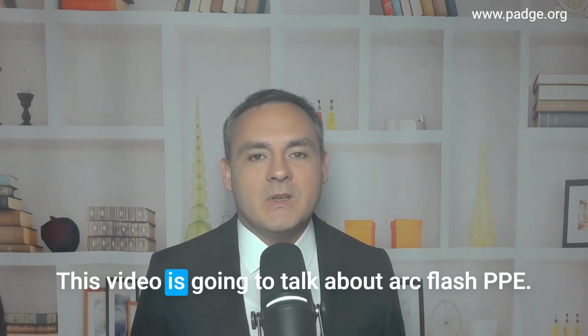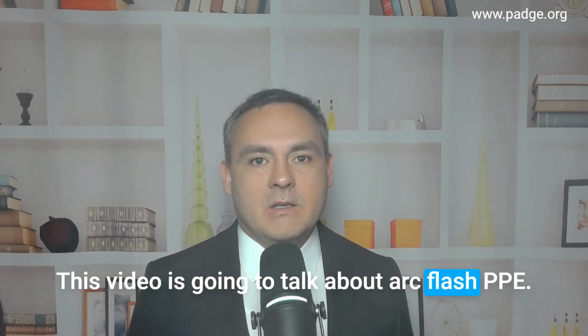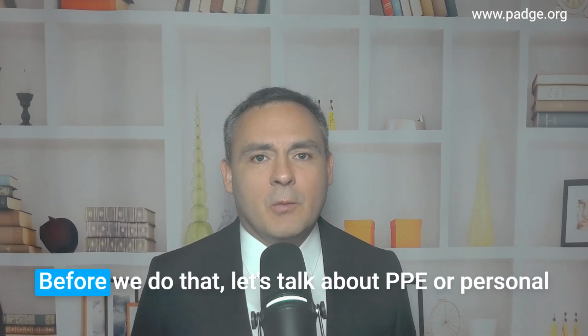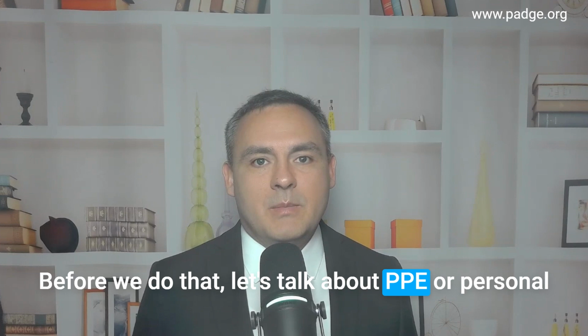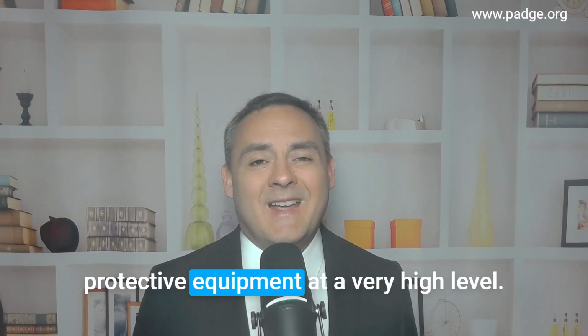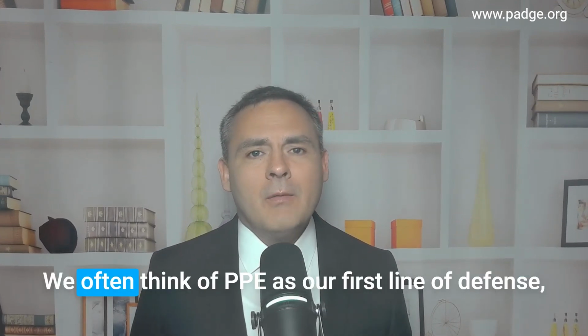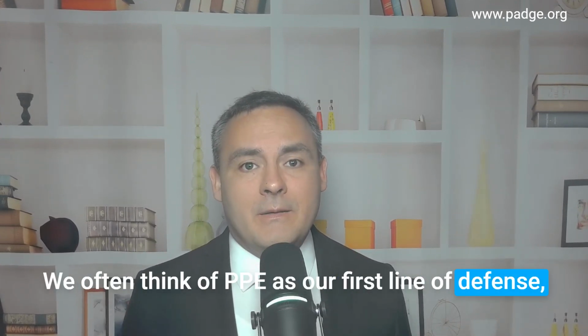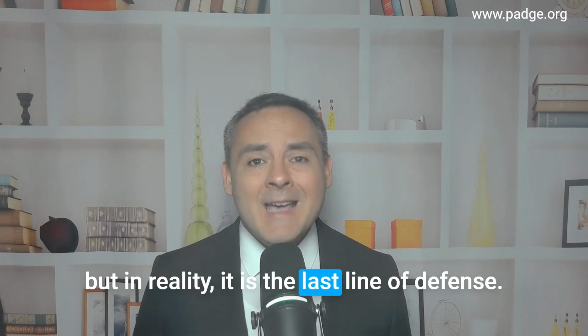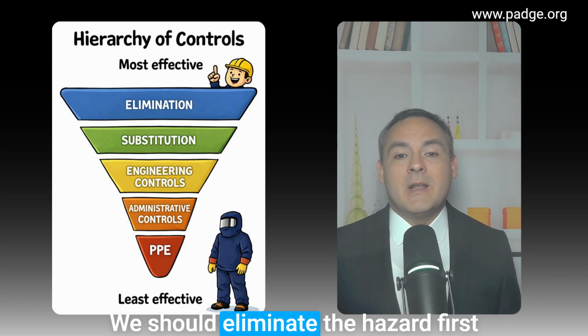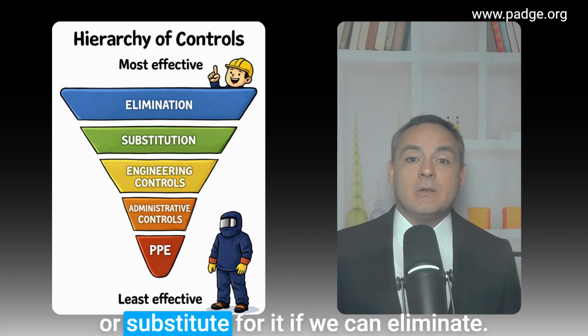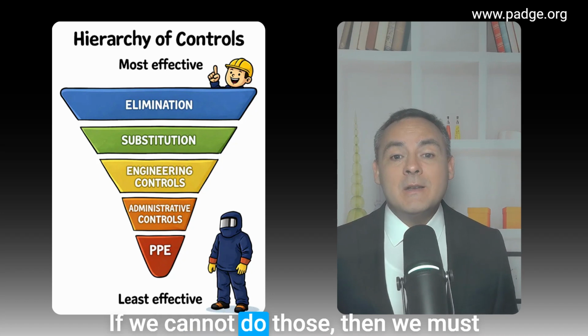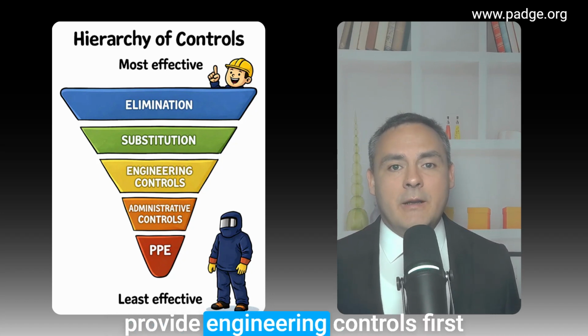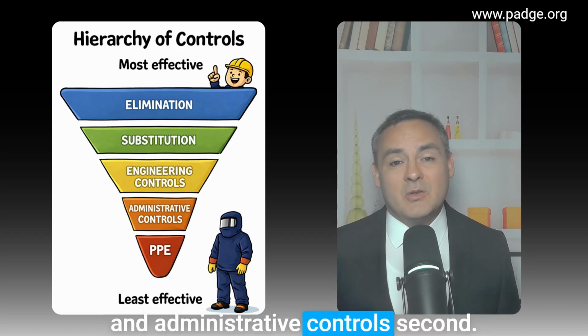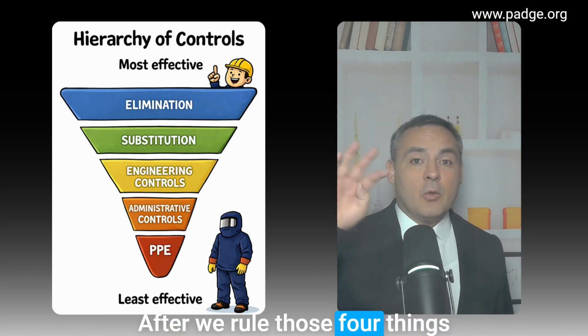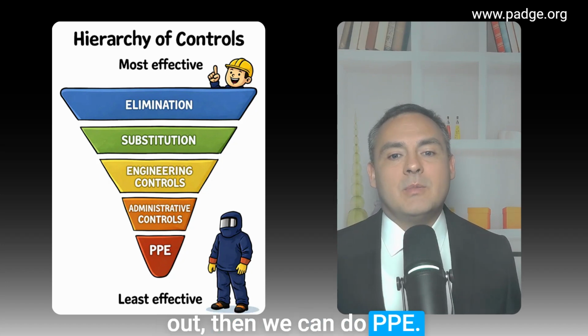This video is going to talk about arc flash PPE. Before we do that, let's talk about PPE, or personal protective equipment, at a very high level. We often think of PPE as our first line of defense, but in reality, it is the last line of defense. We should eliminate the hazard first, or substitute for it if we can't eliminate it. If we cannot do those, then we must provide engineering controls first and administrative controls second. After we rule those four things out, then we can do PPE.